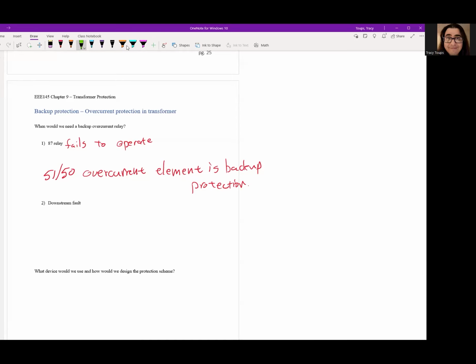If you're running mechanical relays, you will actually have to have a separate mechanical relay for your overcurrent element. You'll need 3 because you have 1 for each phase. So if you're running a transformer protection package with mechanical relays, you're going to have 3 differentials, 1 for A, B, and C phase. You're going to have a minimum of 3 overcurrent relays for A, B, and C phase. You'll probably have a 4th one for the neutral as well. But just remember, in microprocessor relays, this is all just one box. But that box has about 500 settings, so you need to know what they all are, or at least the majority of them. So the 50-51 overcurrent element is our backup, so we're going to focus on that.